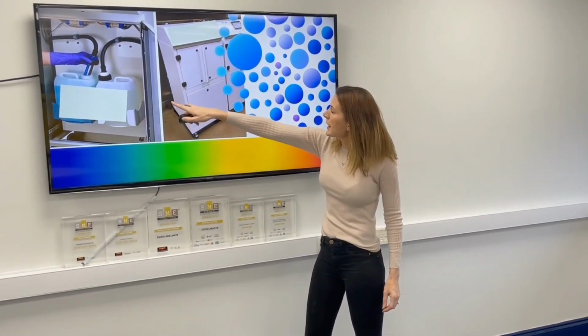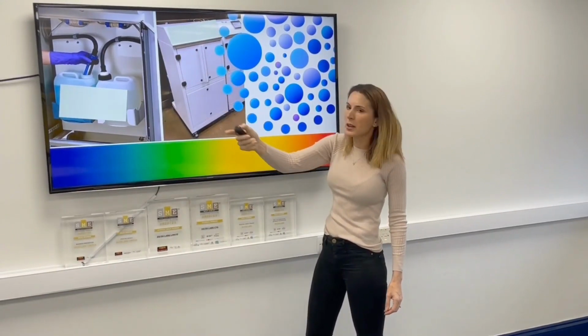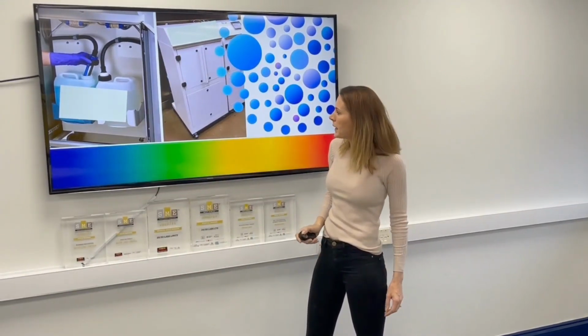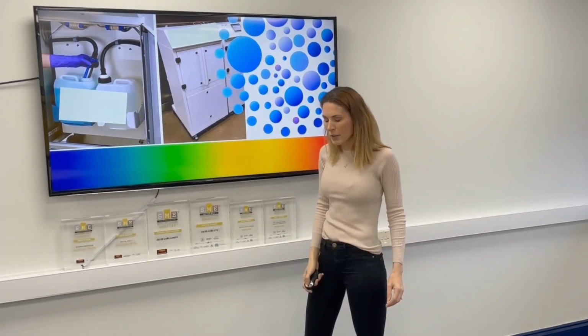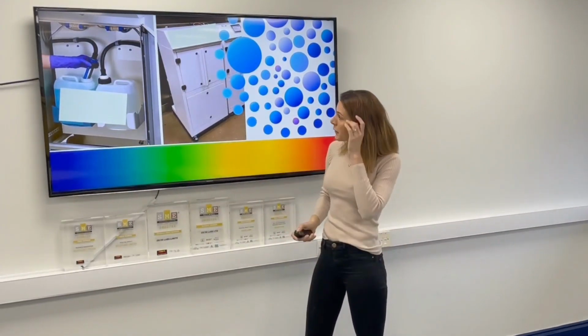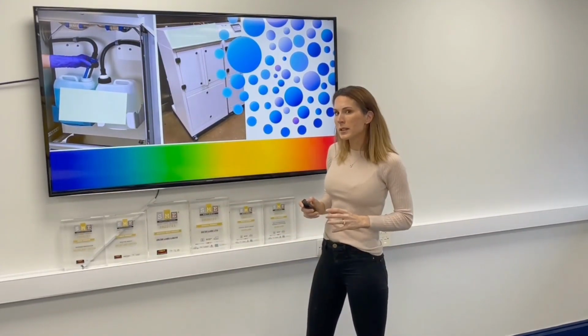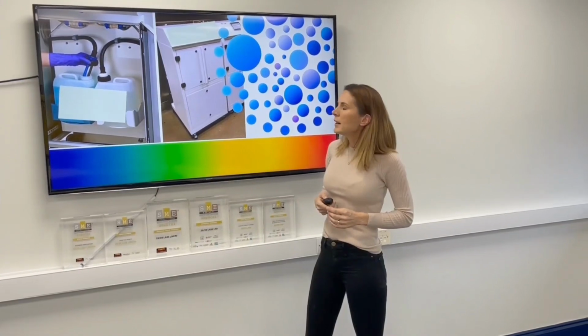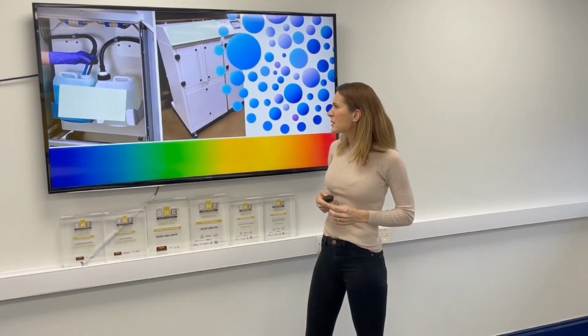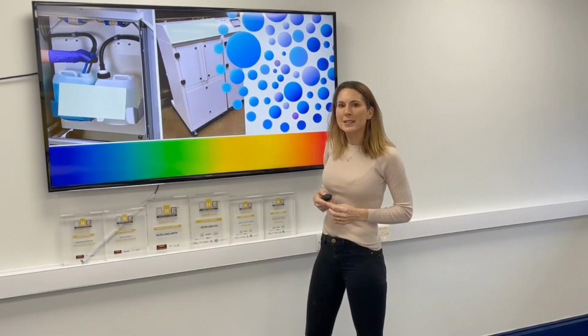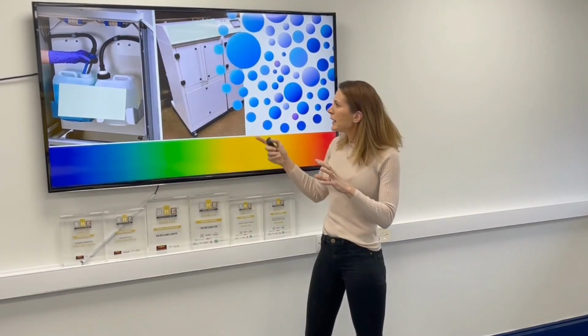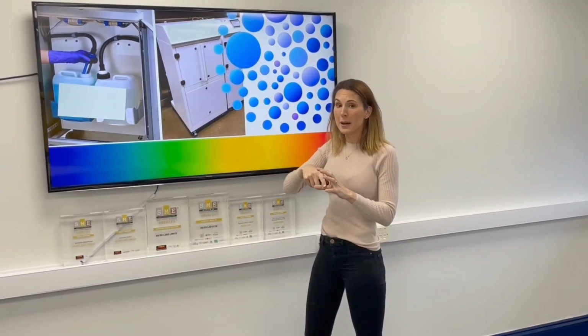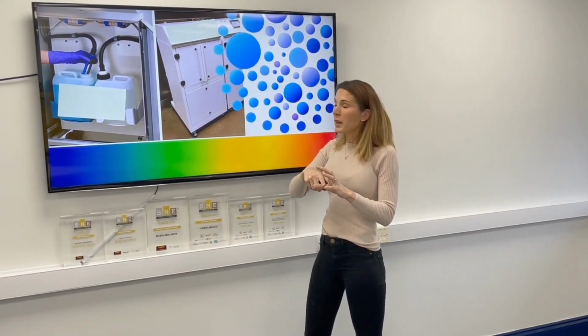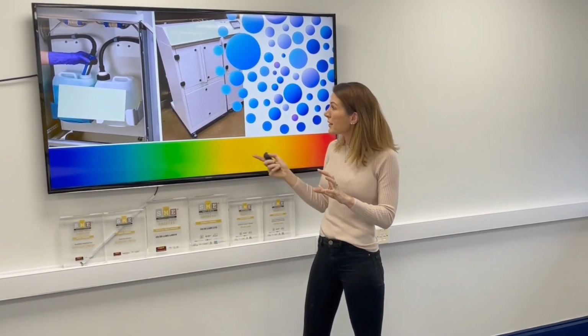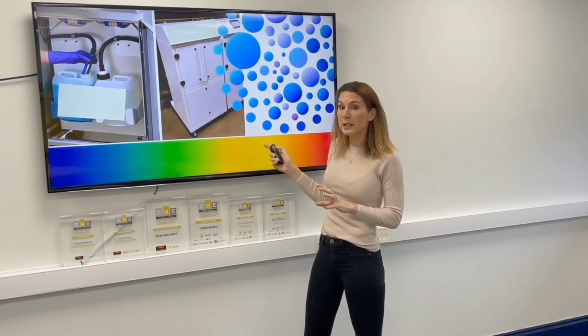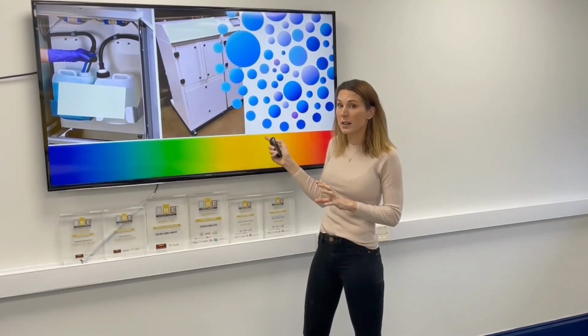We mix these A and B chemicals, we get chlorine dioxide, and we dose the machine with 5 parts per million, and all your bacteria is gone. This is in a number of hospitals in the UK, which is slightly concerning, considering that the machine they're dosing into has peracetic acid, and it used the RO water to dilute that peracetic acid. Well, that peracetic acid, which is a medical device, is now being diluted with chlorine dioxide, which is an oxidizer.